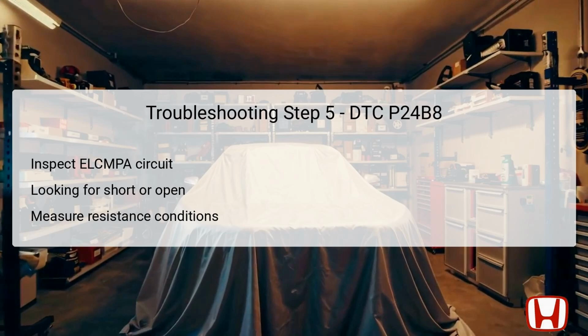Additionally, conduct a short circuit check to ground, which should yield more than 1 mega-ohm if the circuit remains intact. This thorough inspection will help identify if issues are arising due to faulty wiring or connections as they relate to the ELCMPA, furthering the diagnostic process.